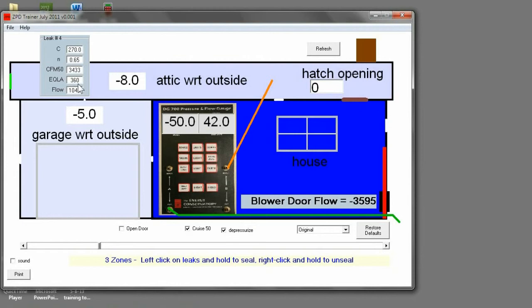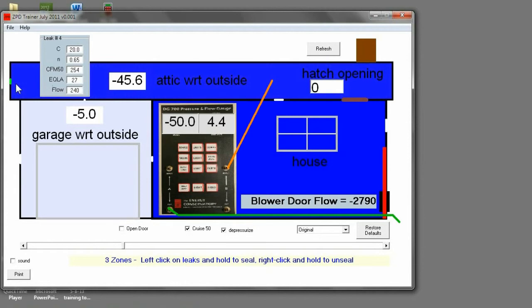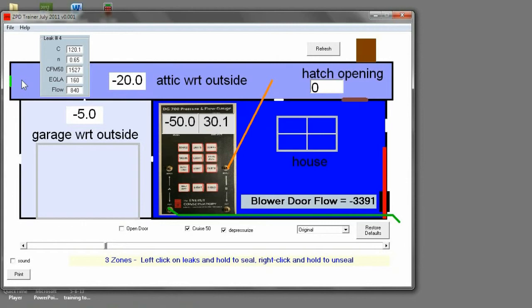You can simulate adding and removing roof vents to see how that affects your CFM50 and your attic numbers. As you make the hole smaller, you'll notice the blower number goes down and our pressure and color become more like the house. As we make that hole bigger, as we add roof vents, our blower door number goes up and our attic pressure becomes closer to the outside pressure. So adding roof vents makes the house leakier.